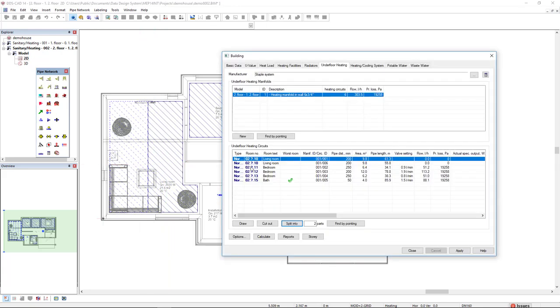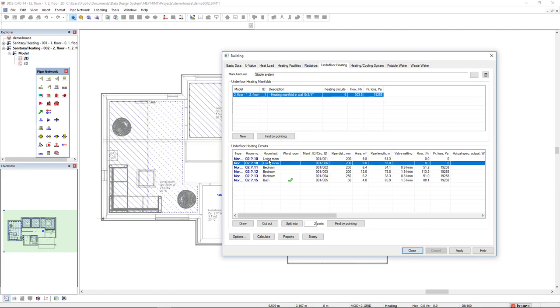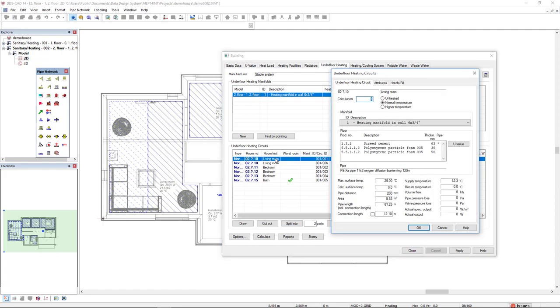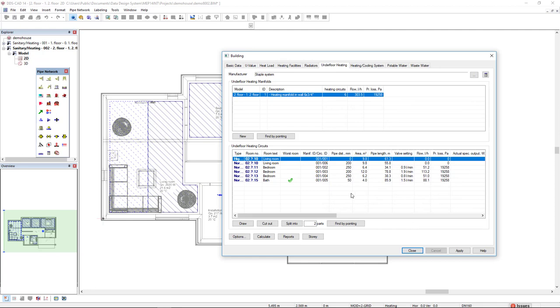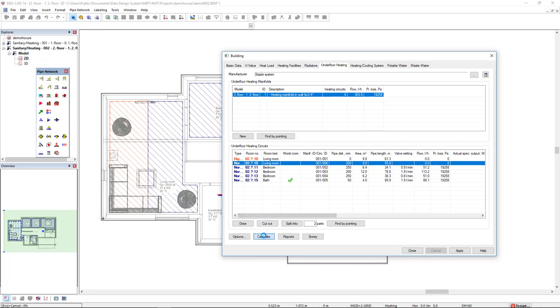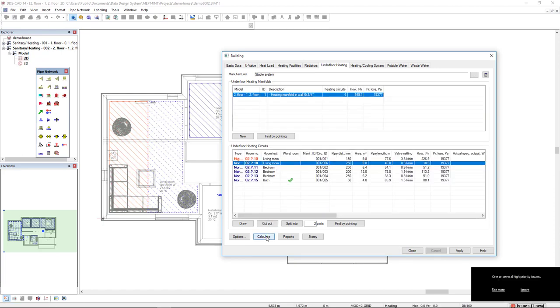Double click here, and I would change the temperature to a higher temperature. If I click OK, we now see the indication in red in the model. And if we recalculate it, we see now that the pipe distance for this circuit or this area is smaller than the blue area on the right.